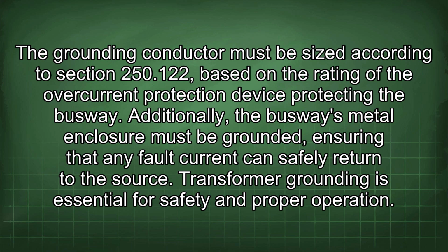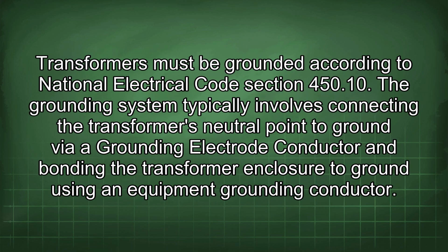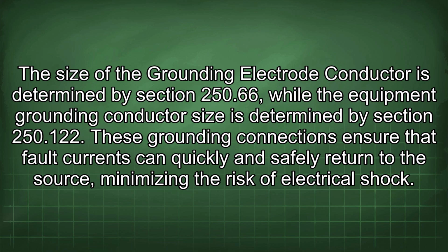Transformer grounding is essential for safety and proper operation. Transformers must be grounded according to National Electrical Code section 450.10. The grounding system typically involves connecting the transformer's neutral point to ground via a grounding electrode conductor and bonding the transformer enclosure to ground using an equipment grounding conductor. The size of the grounding electrode conductor is determined by section 250.66, while the equipment grounding conductor size is determined by section 250.122.